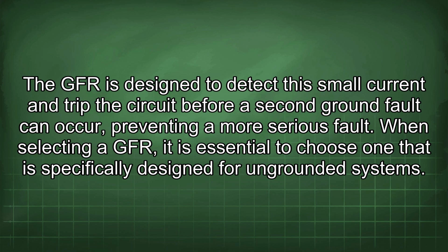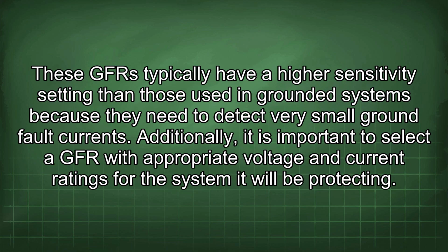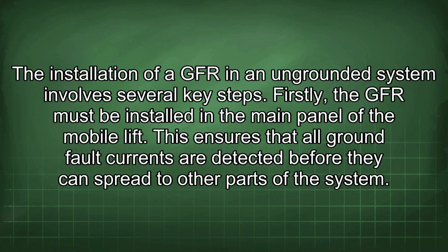When selecting a GFR, it is essential to choose one that is specifically designed for ungrounded systems. These GFRs typically have a higher sensitivity setting than those used in grounded systems because they need to detect very small ground fault currents. Additionally, it is important to select a GFR with appropriate voltage and current ratings for the system it will be protecting. The installation of a GFR in an ungrounded system involves several key steps. Firstly, the GFR must be installed in the main panel of the mobile lift. This ensures that all ground fault currents are detected before they can spread to other parts of the system.